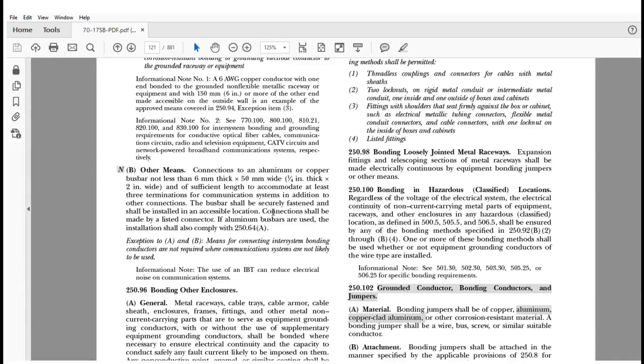Okay? Here's another important aspect of this new subsection here. It says, connections shall be made by a listed connector. If aluminum bus bars are used, the installation shall also comply with 250.64(A). All right? So it's not prohibiting aluminum. It's not prohibiting this application. It's saying, look, we're going to give you the ability to bring all those other systems that you want, that CSST bonding, all that, to a location.